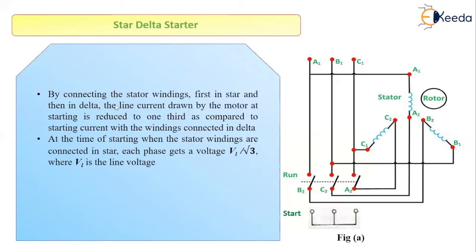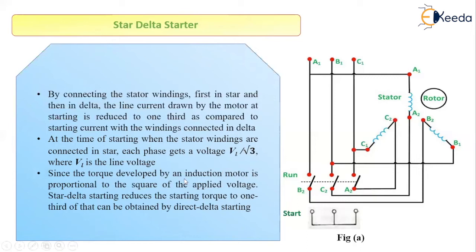When the stator windings are connected in star at starting, we know that V_phase equals V_L divided by root 3, where V_L is the line voltage. So each phase will get a reduced voltage that is 1 by root 3 times the actual line voltage. Also, the torque developed in the induction motor is directly proportional to the square of the applied voltage. So as the reduced voltage is applied, the starting torque will also be reduced to one third of what would be obtained by direct delta starting. So our current will be reduced by one third, and our starting torque will also be reduced by one third.